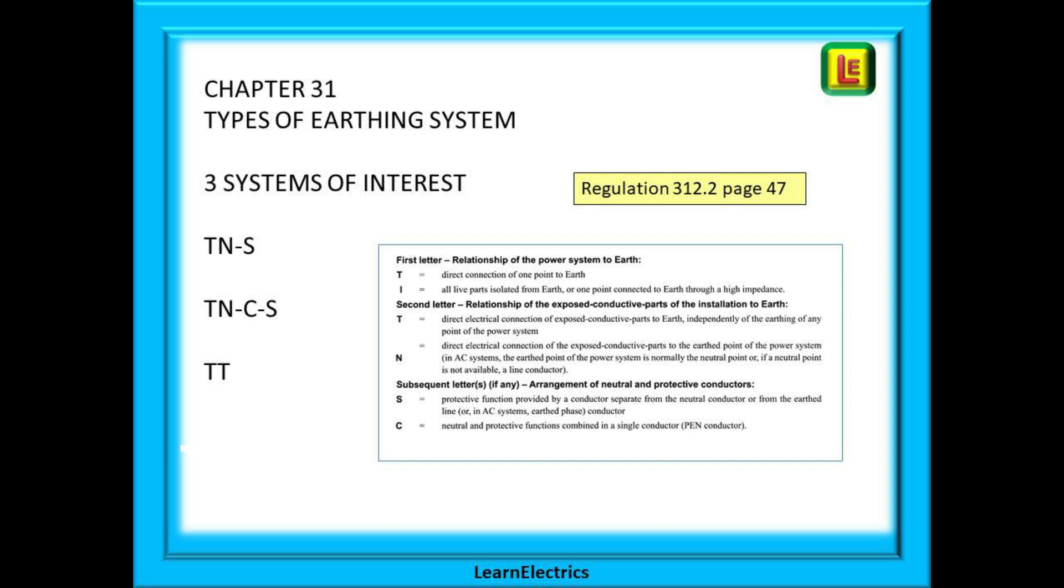The table on page 47 describes how code letters are used. The code letters that matter to us mean T for earth. The Latin name for earth is terra, a T. N is for neutral. C for combined where the earth and neutral are combined together and use the same conductor. And S is for separated where the earth and neutral are in separate conductors.